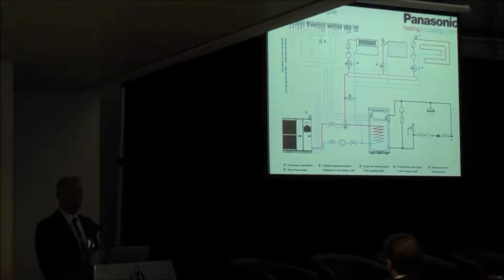If you change settings, obviously it's going to change how efficient the system operates, but in order to change how the system is programmed, you have to press a certain few buttons on the controller in a specific sequence, which gives you access to the setting code. So it's not a simple thing to do, you know.